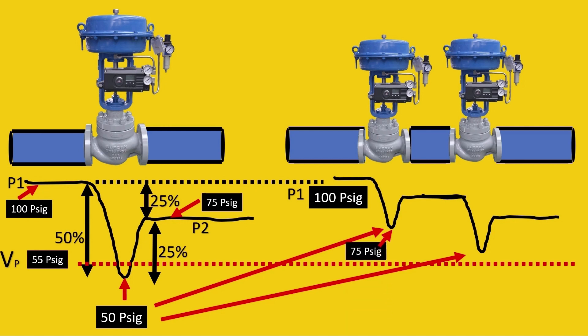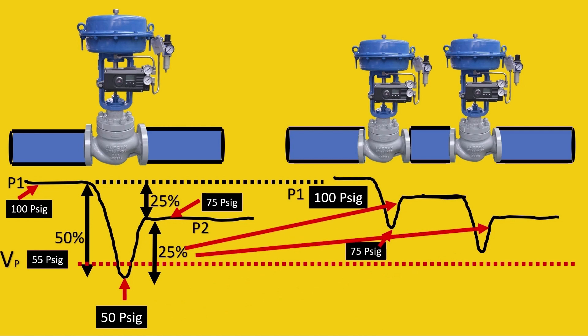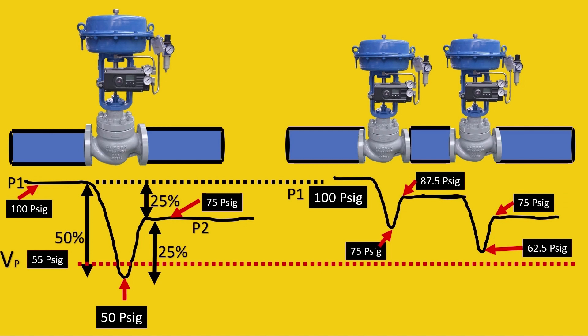It is going to be 25%. The recovery also will be divided between the two valves, so 25% divided will be 12.5, 12.5. Here 75 plus 12.5 is 87.5 psig. We get the first recovery and again the pressure drop is going to be 25%, so 25% of 87.5 is 62.5 psig and again the recovery of 12.5 which is 75 psig.